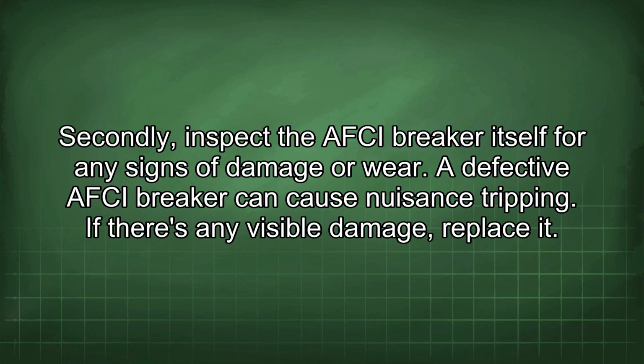Secondly, inspect the AFCI breaker itself for any signs of damage or wear. A defective AFCI breaker can cause nuisance tripping. If there is any visible damage, replace it.